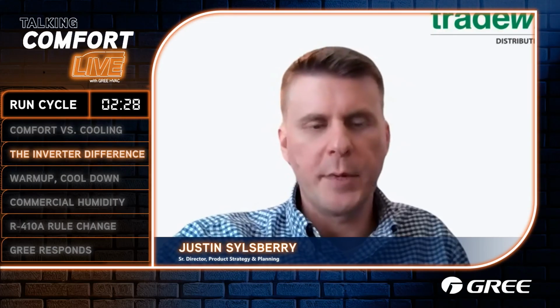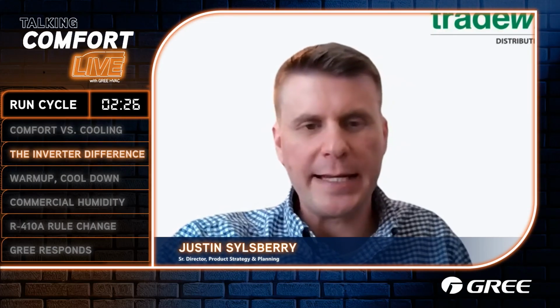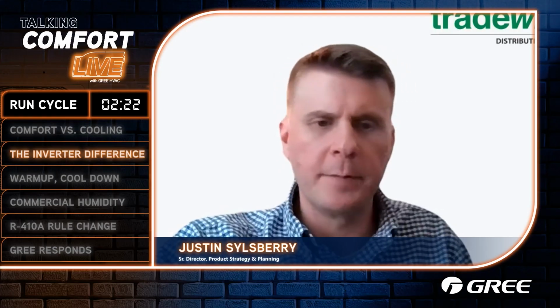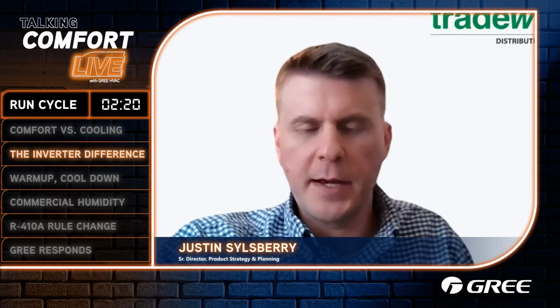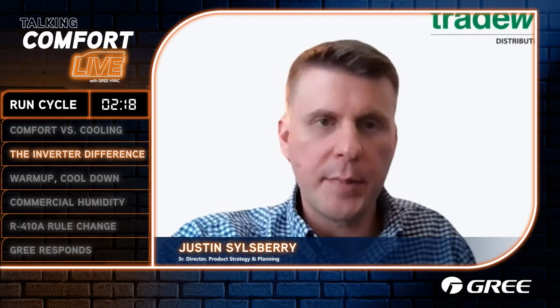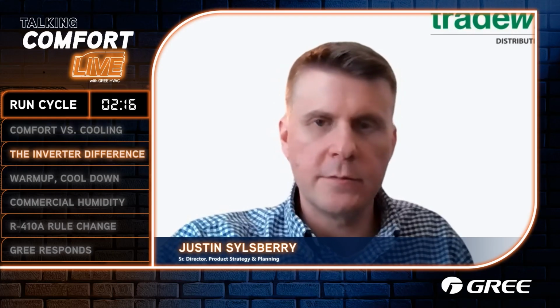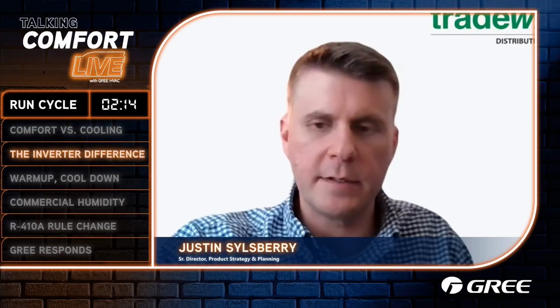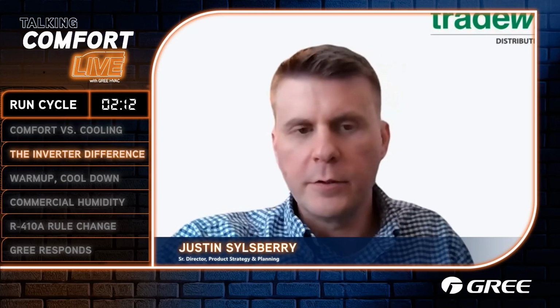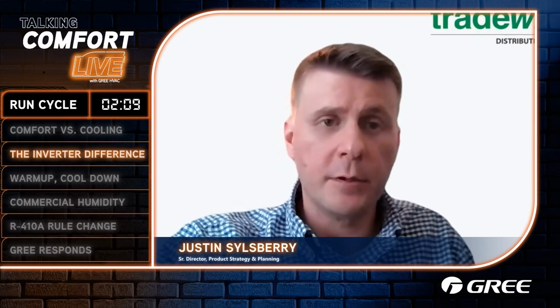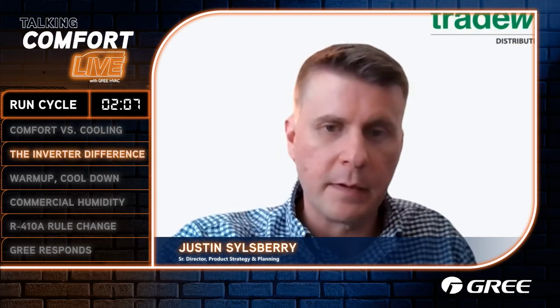You'll get that information from our extended ratings, which will show you a total cooling number and a sensible number. From that you can get the latent capacity—latent is just total minus sensible. So you'll utilize those extended ratings, which are available on greecomfort.com.